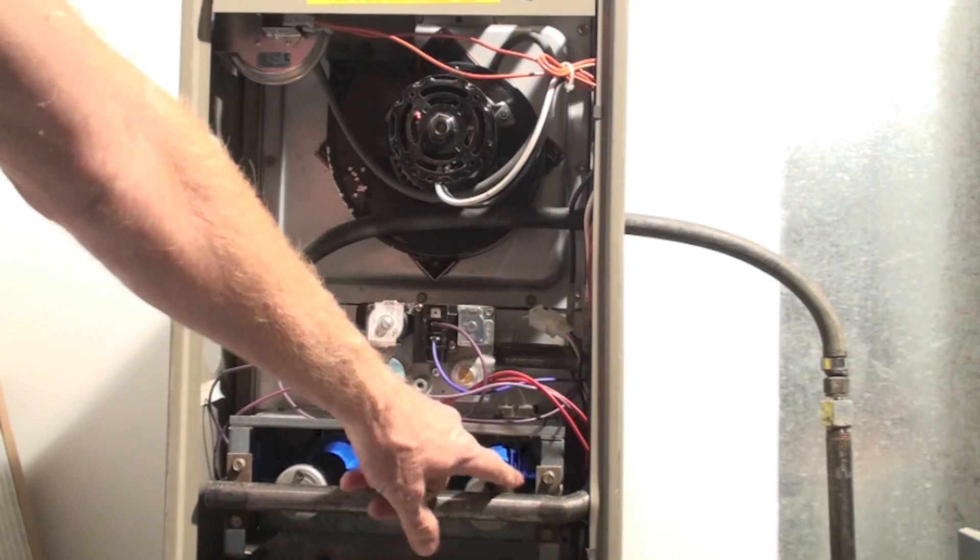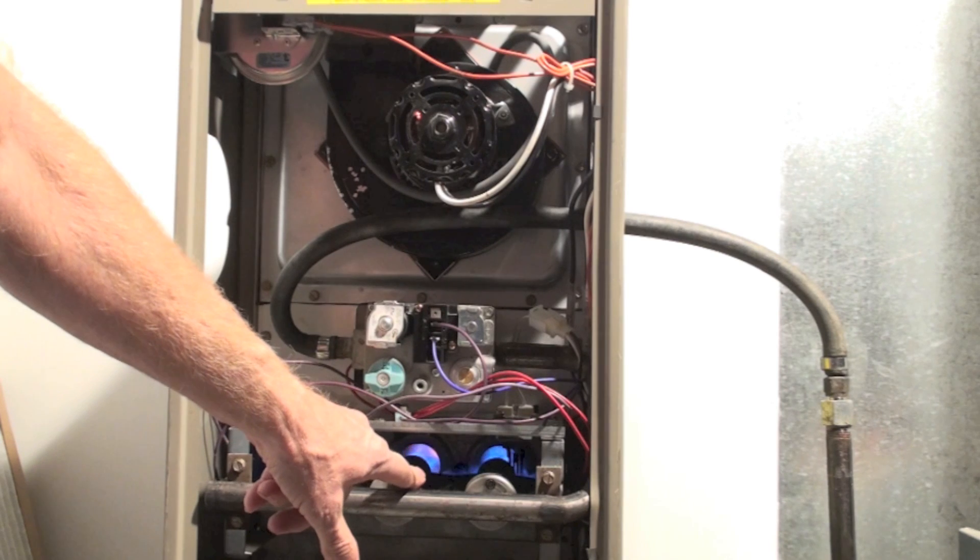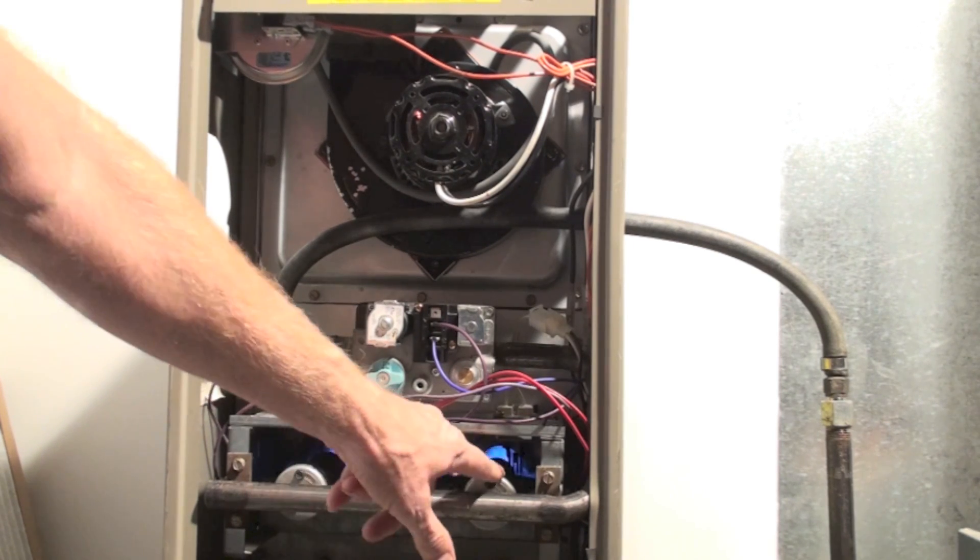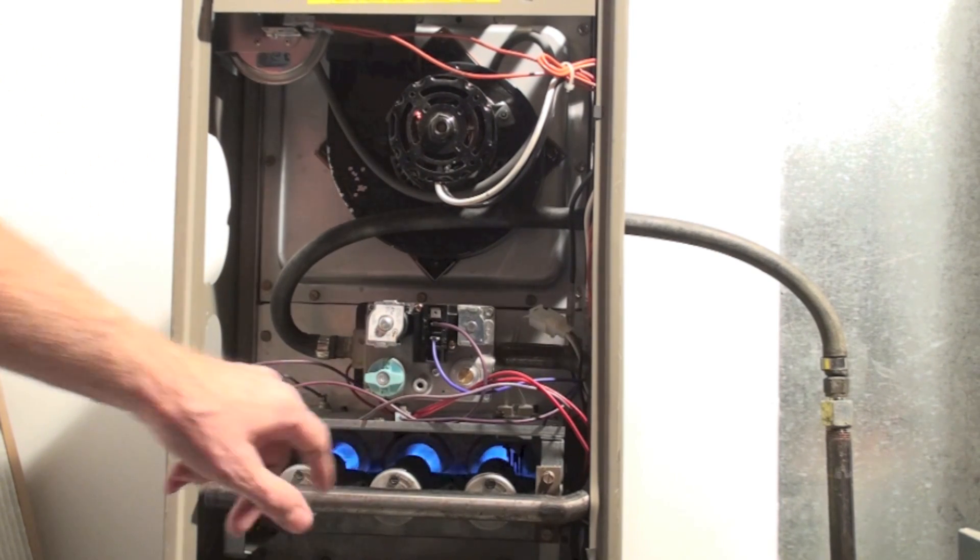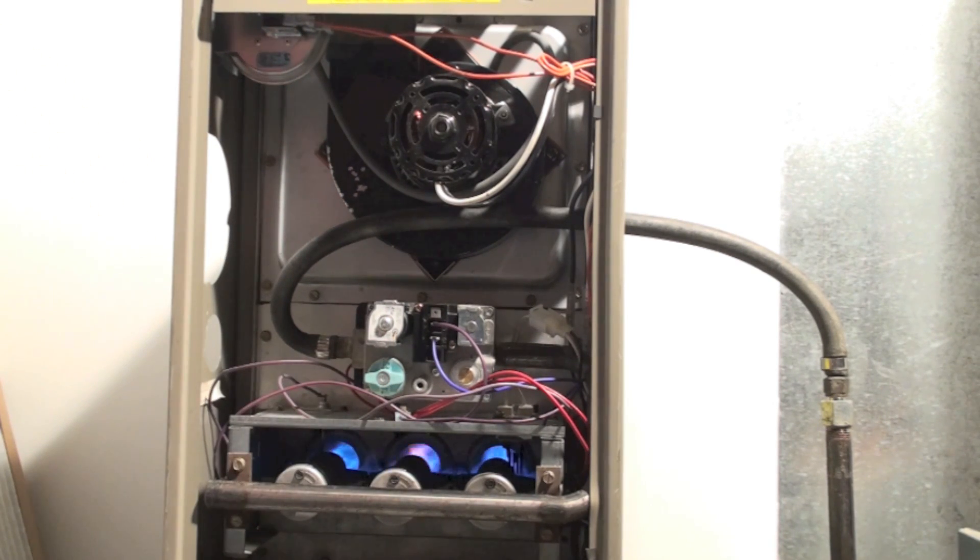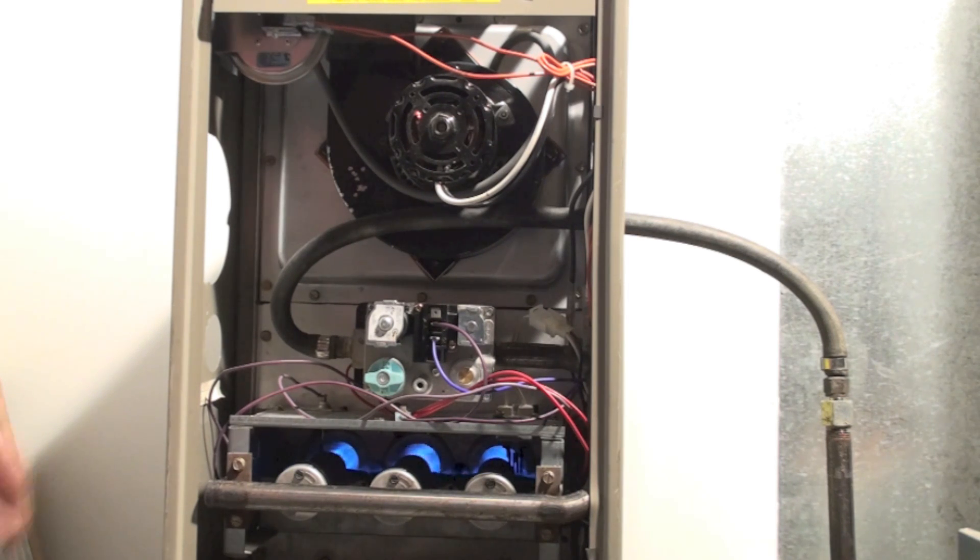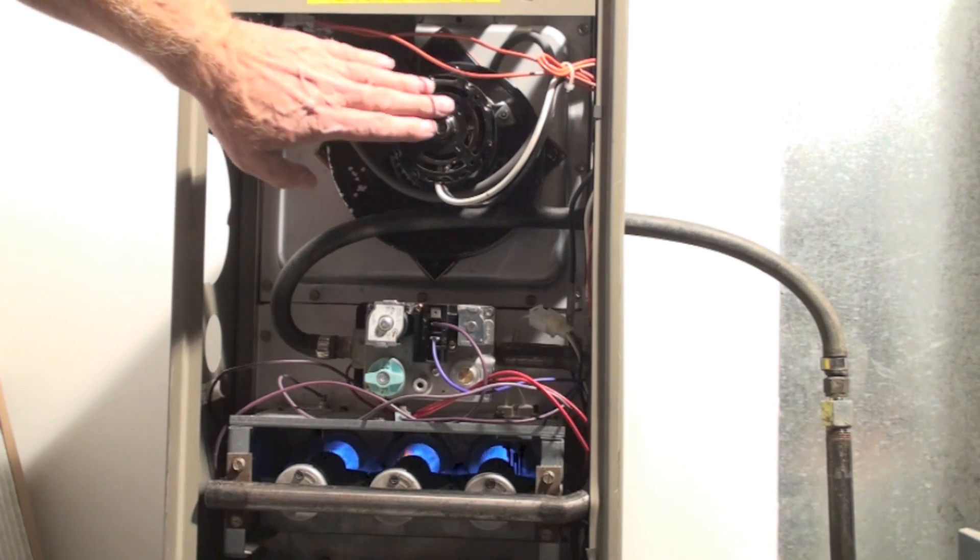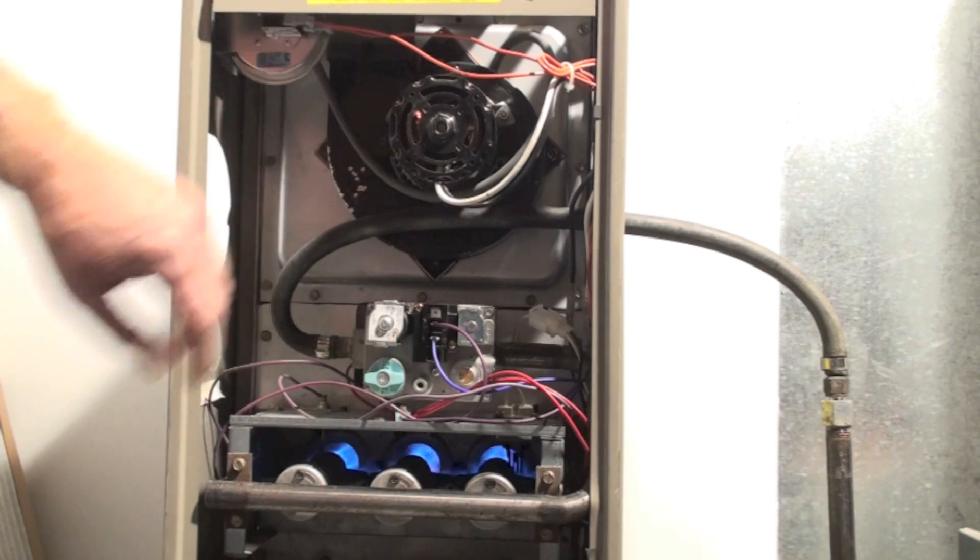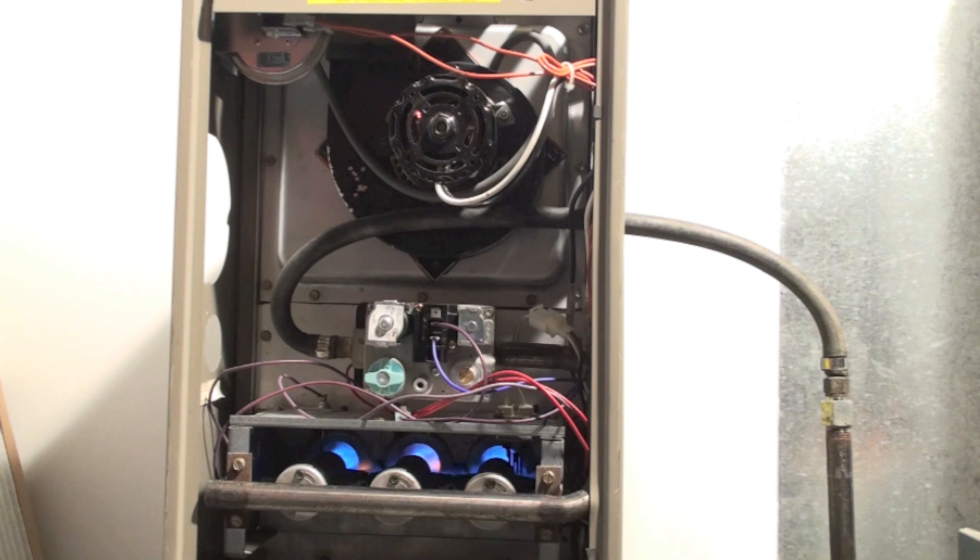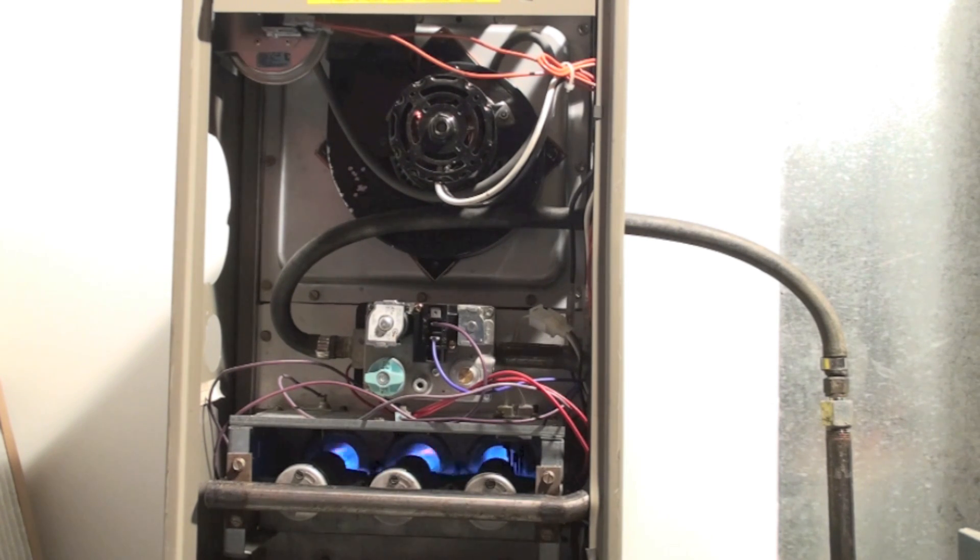We have a hot surface igniter right here, so it's going to pass from this one to this one to this one. But you're looking at that and you're listening for unusual noises in this blower—clanks and bongs and stuff. Now the inducer or the blower just started.